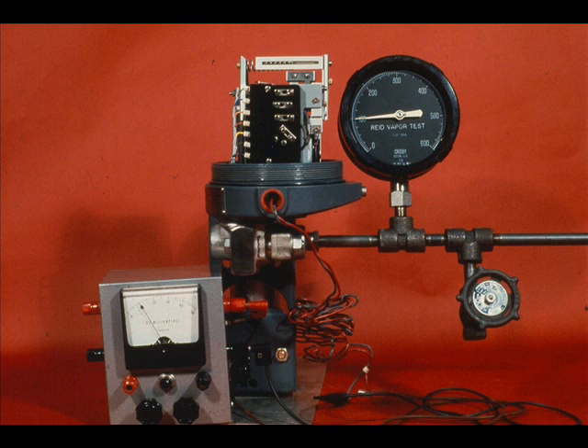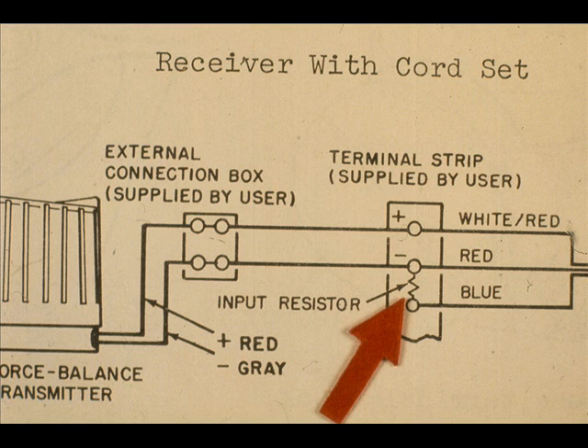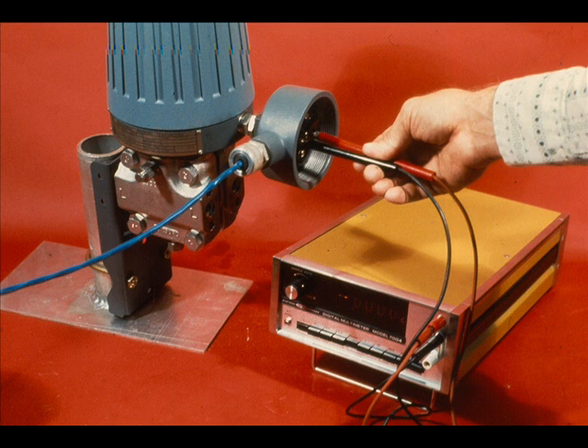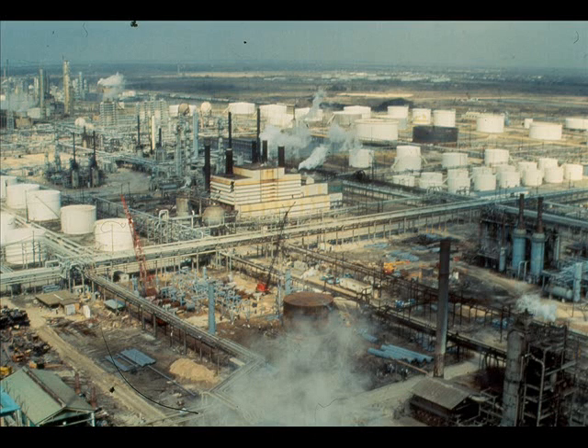The Foxboro gray box calibrator is entirely satisfactory for many installations. Some transmitter circuits have a precision resistor located near the transmitter; a digital voltmeter or a millivolt box connected across the resistor will give satisfactory readouts for zero and calibration purposes. There is no clear-cut calibrating procedure and selection of calibrating tools for all plants, or even within a given plant — a judgment is made for each task.